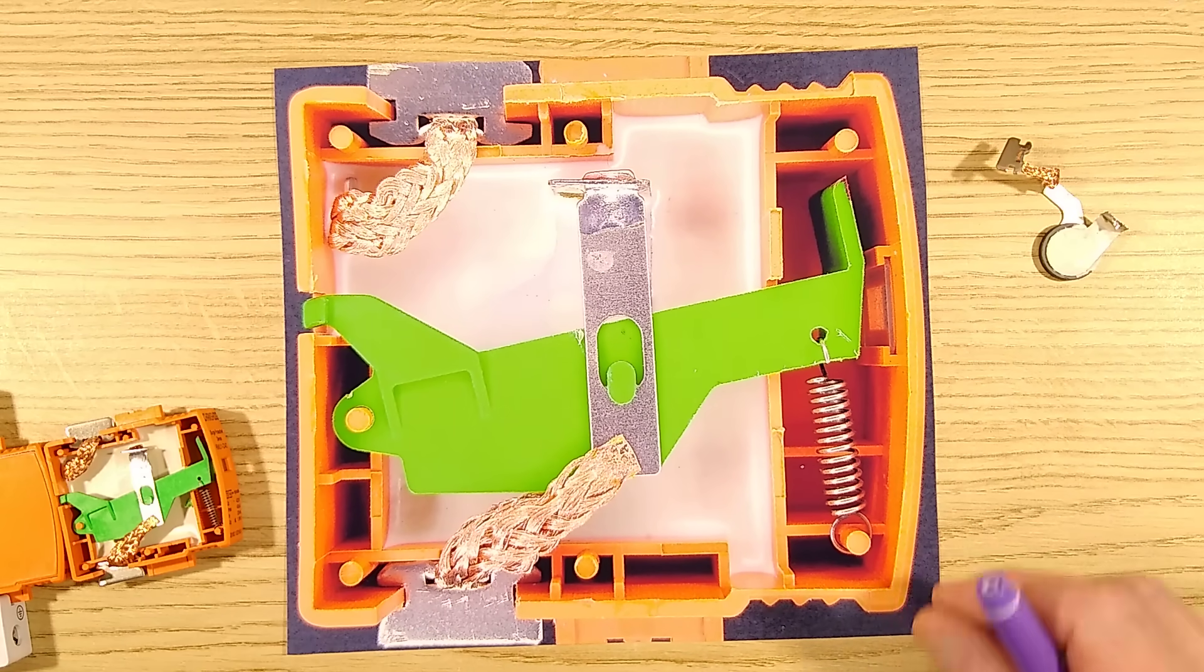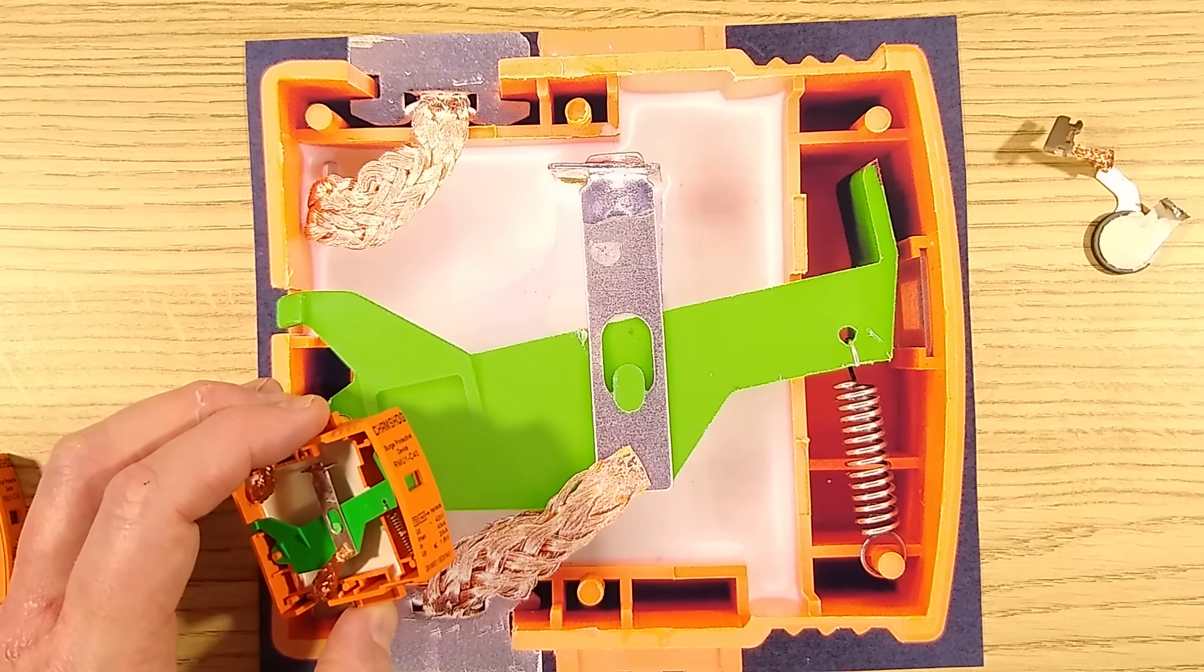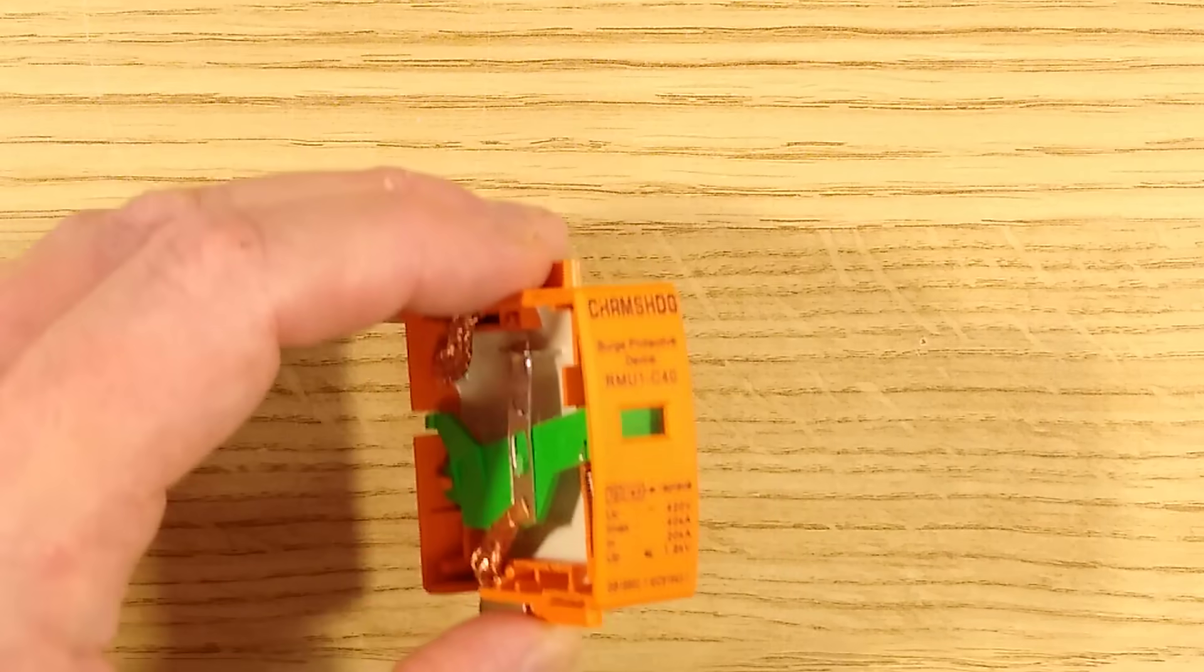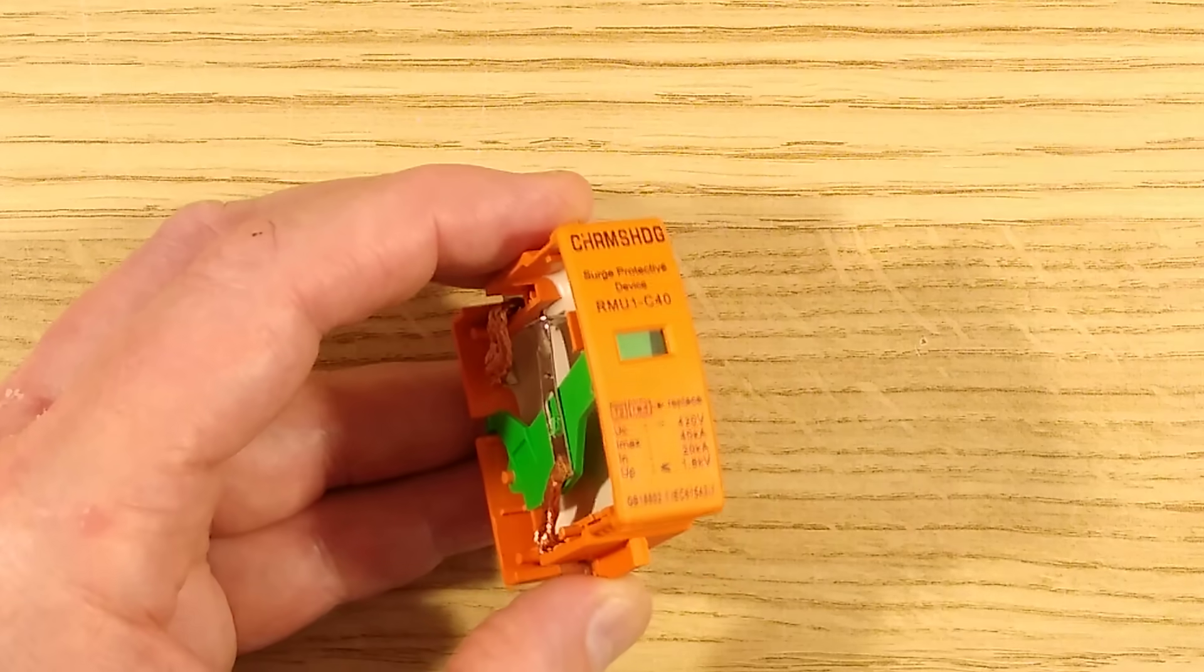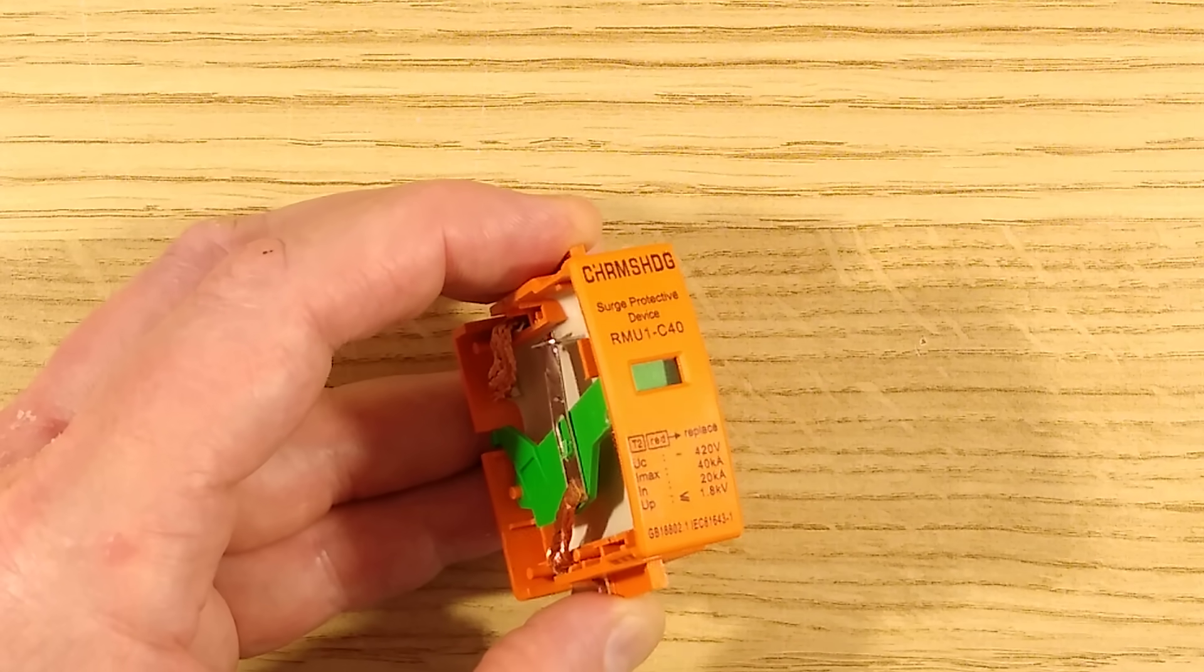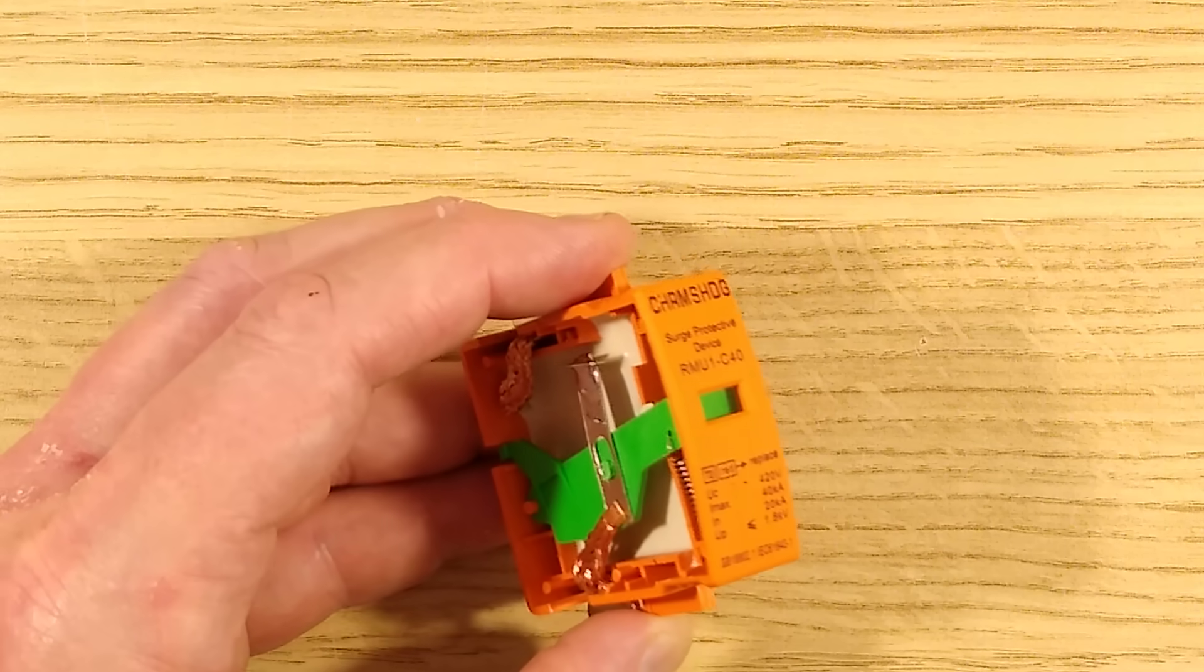However, there is a problem with this. Let me show you what happens when this one trips. So I'll zoom in again. And you can see that this one has the wee green window there. Let me just focus down on that. So you can see it's green, which means that is good, it's operating. However, when it trips, let me find something to trip it with here, a pair of long-nose pliers.